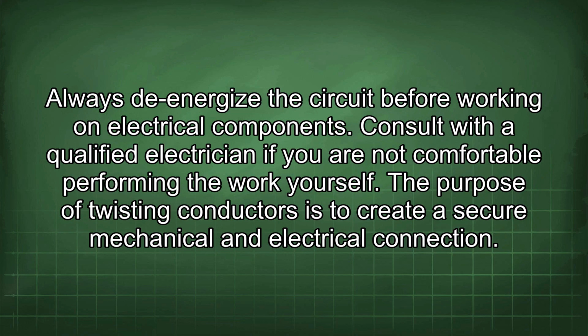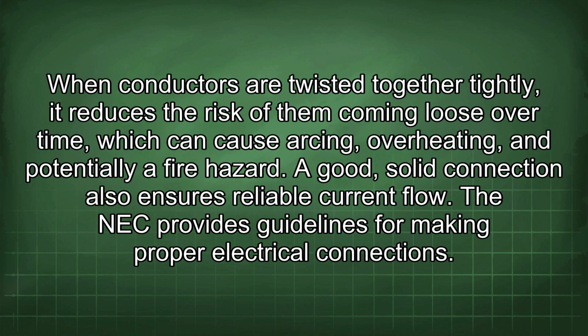The purpose of twisting conductors is to create a secure mechanical and electrical connection. When conductors are twisted together tightly, it reduces the risk of them coming loose over time, which can cause arcing, overheating, and potentially a fire hazard. A good, solid connection also ensures reliable current flow.